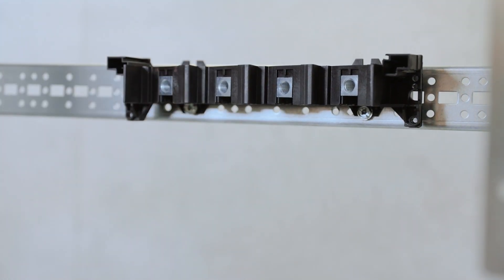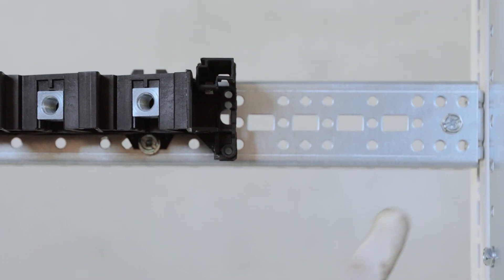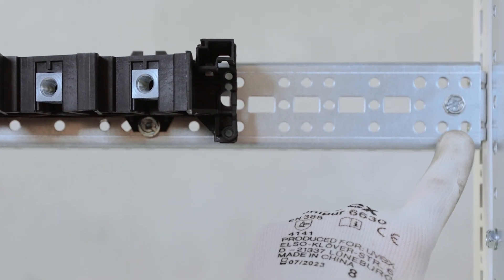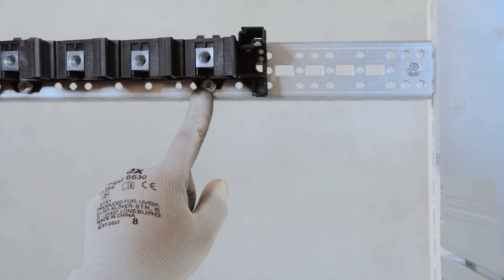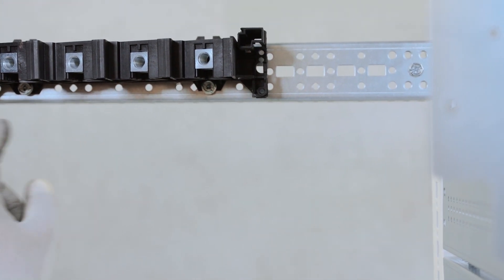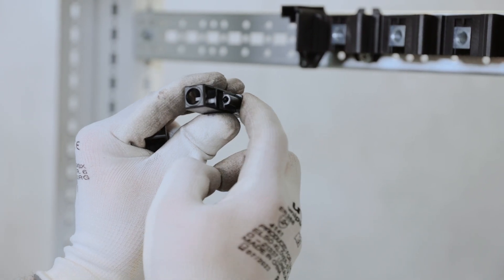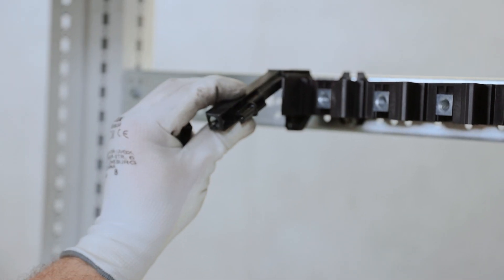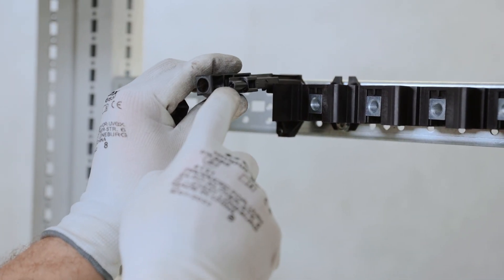Take care that the corners for safety screen holders are located in the outer edges. It's important that the screws are at the bottom. Determine the right distance for the other busbar supports easily by looking for the square holes. They always have a distance of 10 centimeters. For the fixation of the safety screen, first add the accessory part on the holder before clipping it.